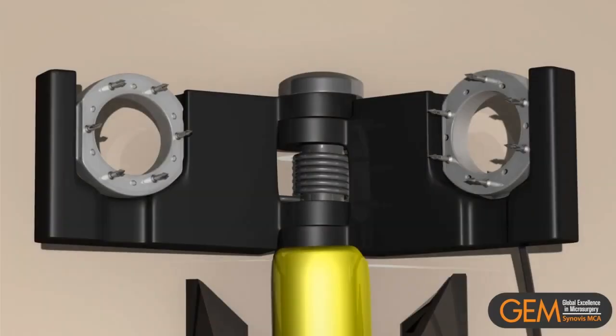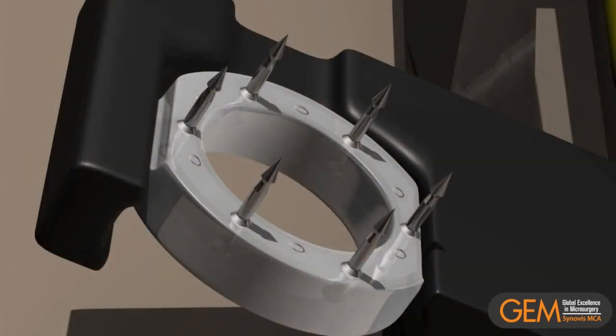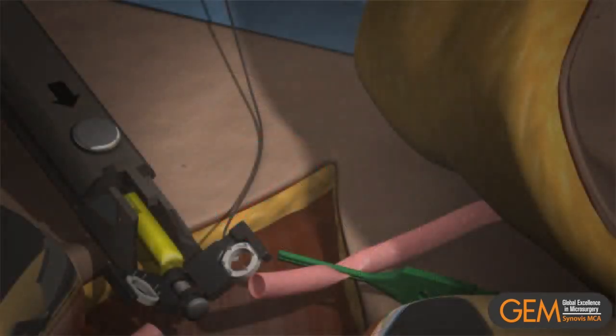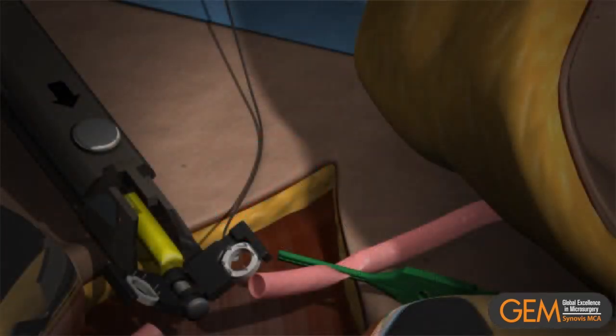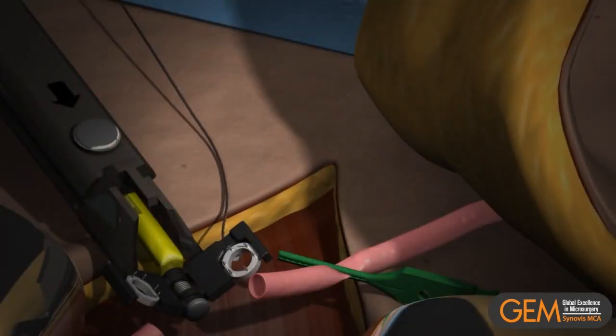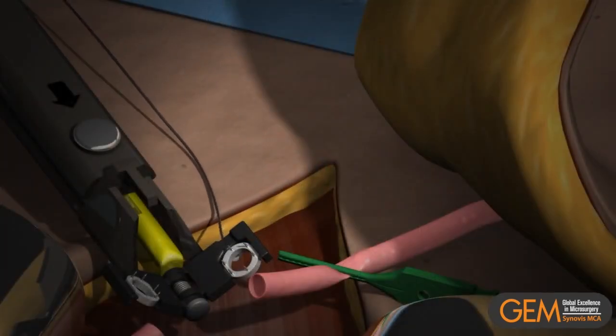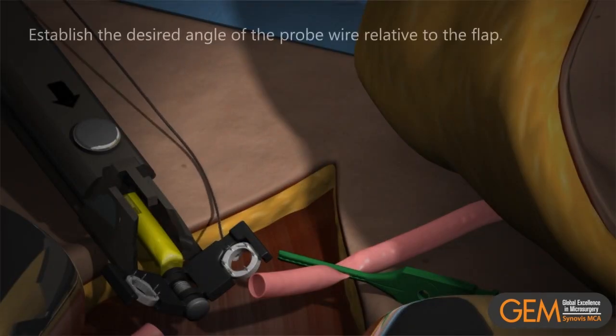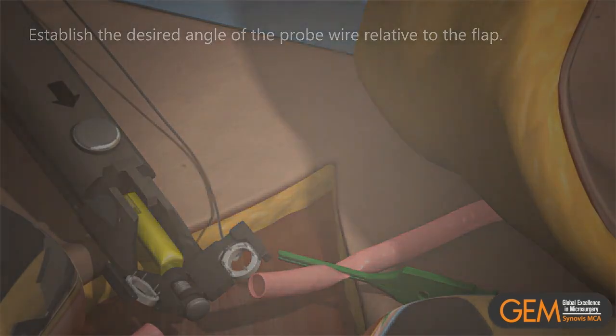Visually inspect to confirm that both rings are seated at the bottom of the U portion of the jaw and that the pins are not bent. If the pins are bent, do not attempt to straighten them. Instead, use a new flow coupler device. Note: to avoid unwanted kinking or twisting of the vessel during positioning of the flap, care should be taken to establish the desired angle of the probe wire relative to the flap and to adjust the anastomotic instrument accordingly before starting the anastomosis.